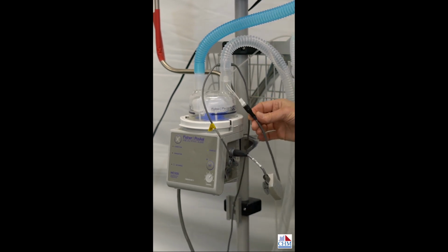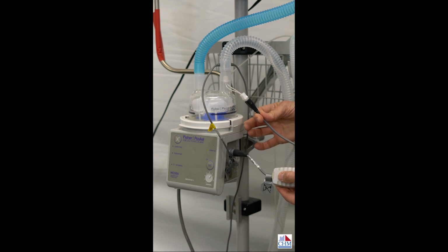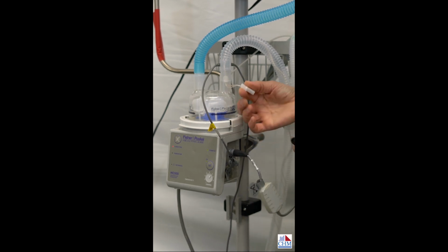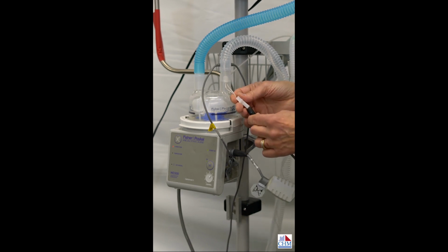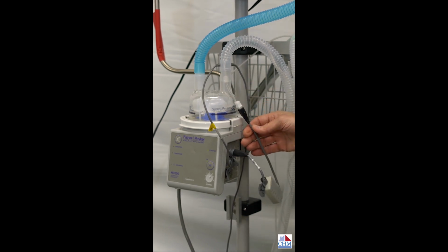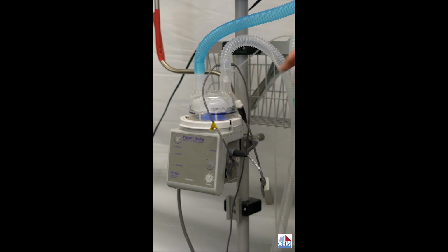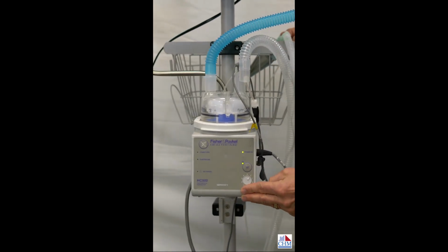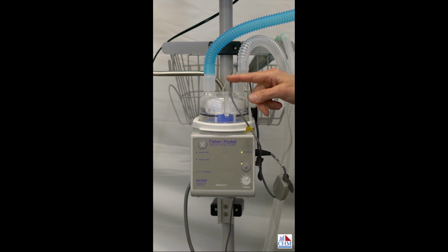The other disconnection can occur here at the other end of the heated wire adapter, where it's actually connected to the tube circuit itself. So those are easy to fix and usually pretty obvious because you can see that they're disconnected. The problem runs into breakage in the wires that we can't see. So when this is used over and over again, and these wires, especially at the corners here, get bent, eventually they break on the inside, but we can't see them. So the easiest thing to do to try to troubleshoot is to exchange them, and we'll just go through it step by step, starting with the most common problem.